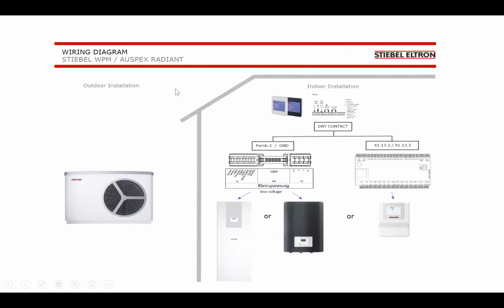What we do - and this is based on an Auspex manifold actuator system, but it's the same whether it's Uponor, Auspex, or Rehau - the reason it's the same is because most of those manifold systems have got a dry contact, which is just used to initiate the boiler. So if you've got a Rehau system and a gas boiler outside, basically all the manifold system is doing is closing a set of contacts, which gives the boiler a signal to go.